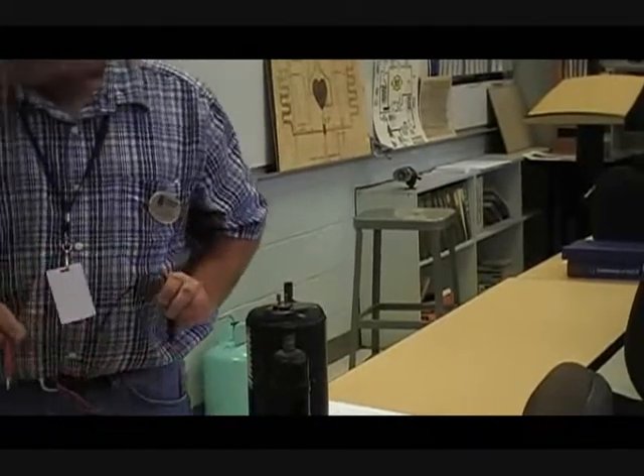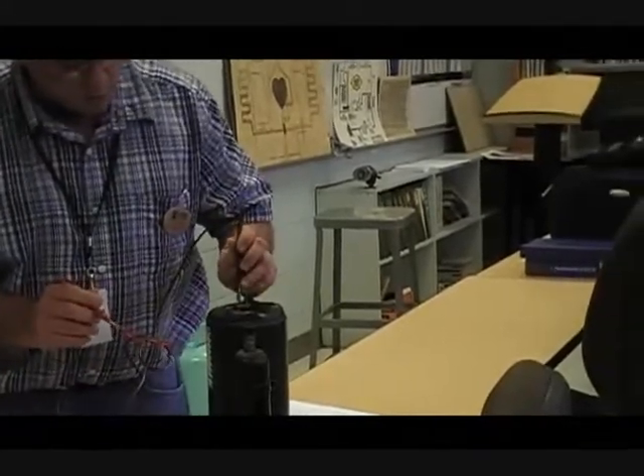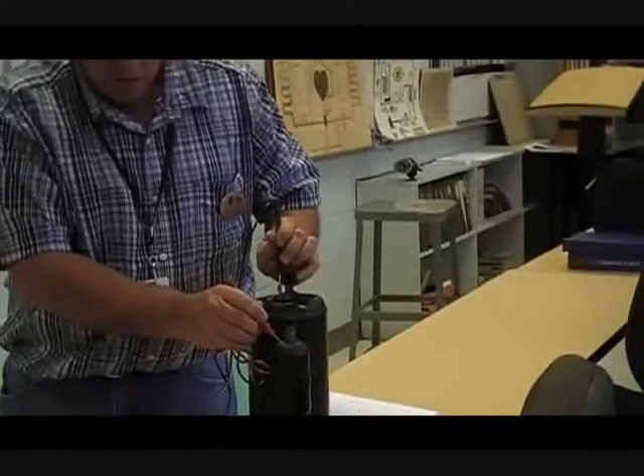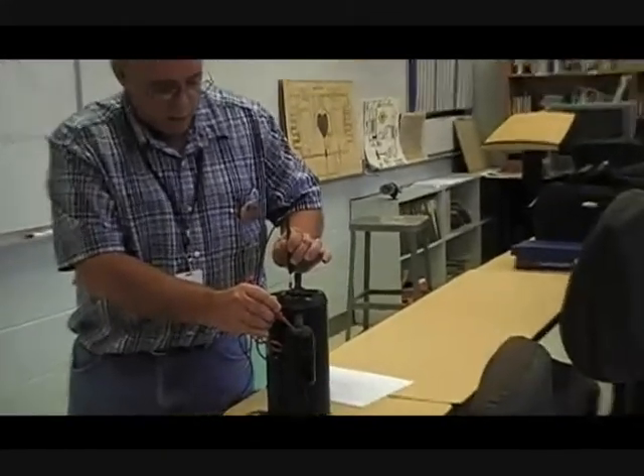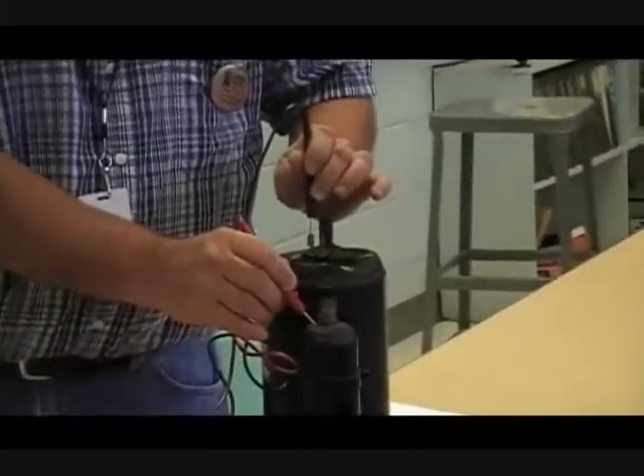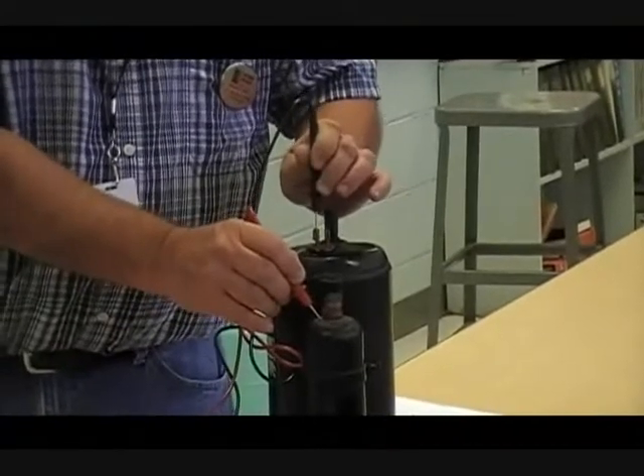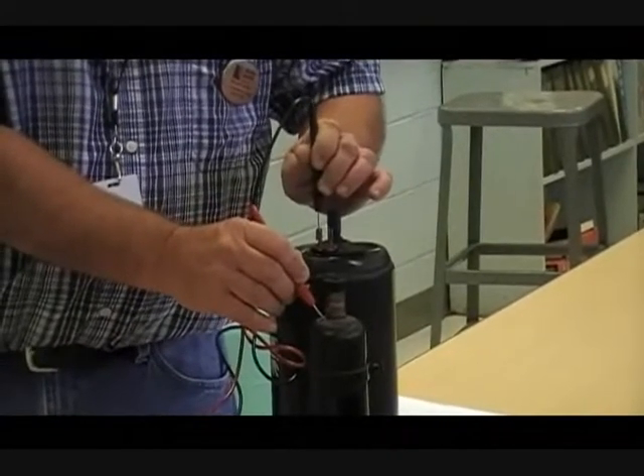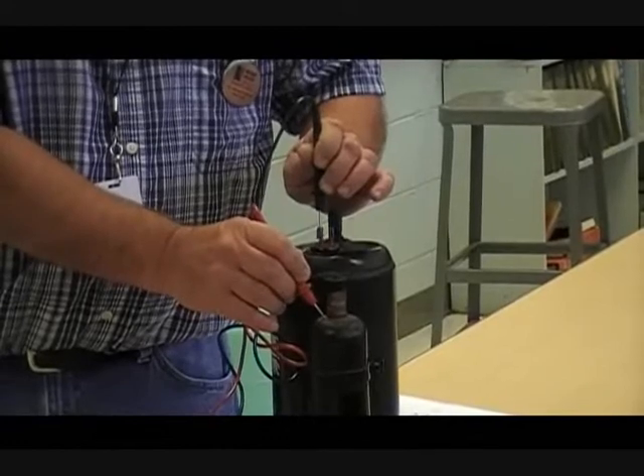In order to troubleshoot this compressor, I want to, number one, make sure that it is not grounded. You want a good ohmmeter for this. If you have an ohmmeter that will not read into the kilo ohms, you may not see a grounded compressor.